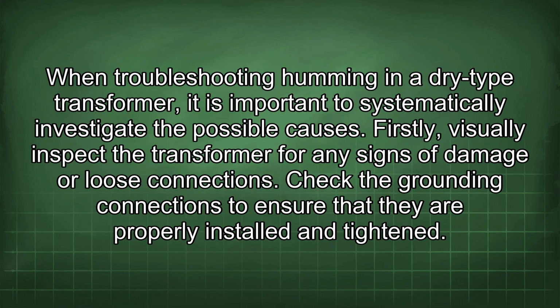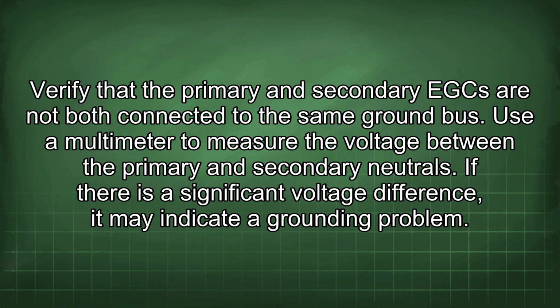When troubleshooting humming in a dry-type transformer, it is important to systematically investigate the possible causes. Firstly, visually inspect the transformer for any signs of damage or loose connections. Check the grounding connections to ensure that they are properly installed and tightened. Verify that the primary and secondary EGC are not both connected to the same ground bus. Use a multimeter to measure the voltage between the primary and secondary neutrals. If there is a significant voltage difference, it may indicate a grounding problem.